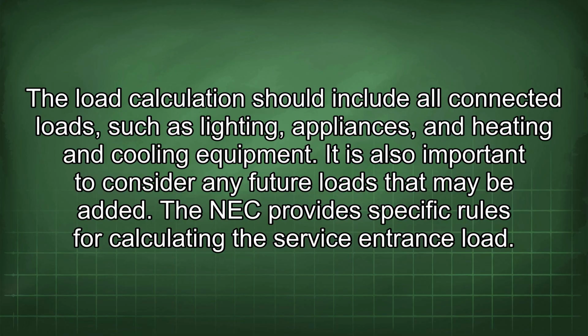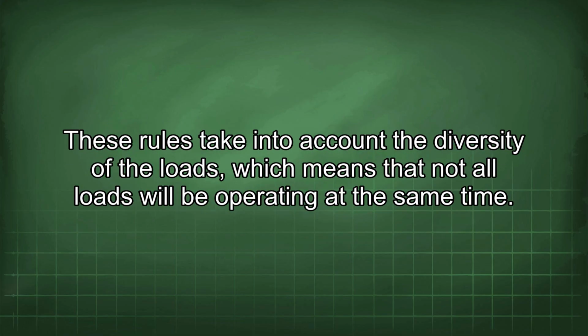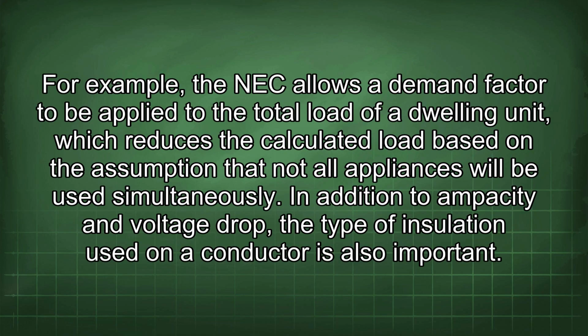The NEC provides specific rules for calculating the service entrance load. These rules take into account the diversity of the loads, which means that not all loads will be operating at the same time. For example, the NEC allows a demand factor to be applied to the total load of a dwelling unit, which reduces the calculated load based on the assumption that not all appliances will be used simultaneously.